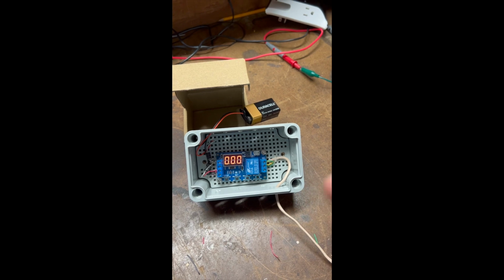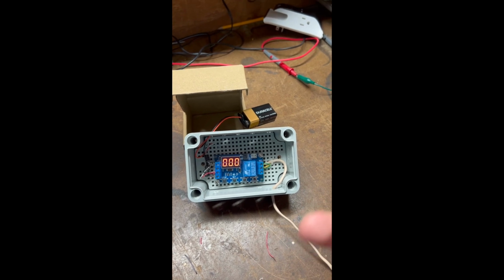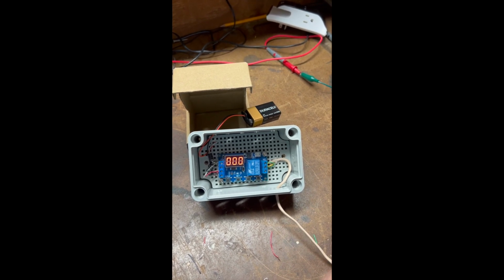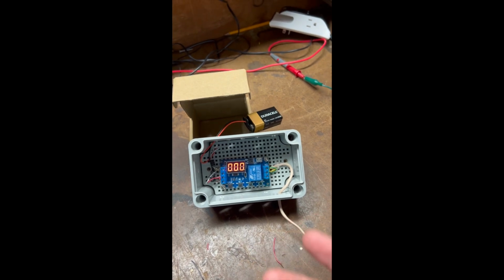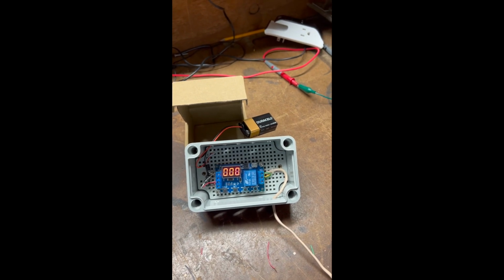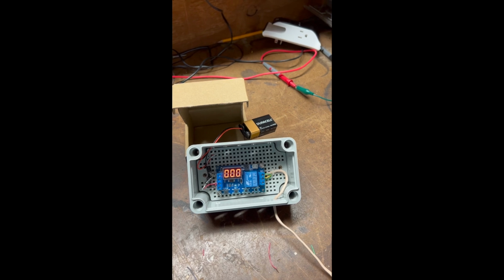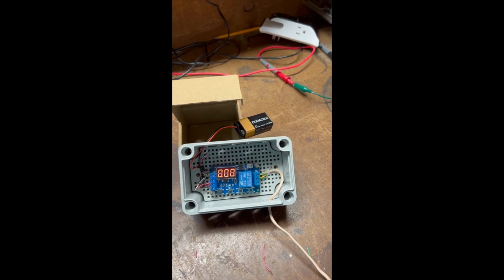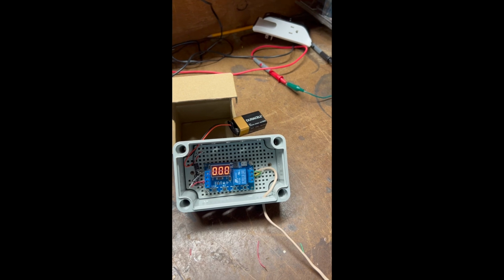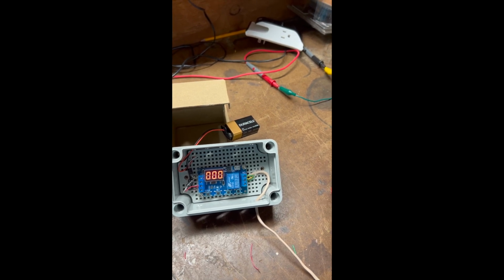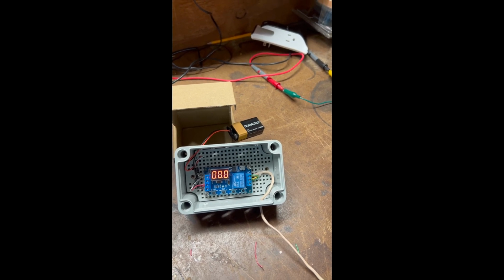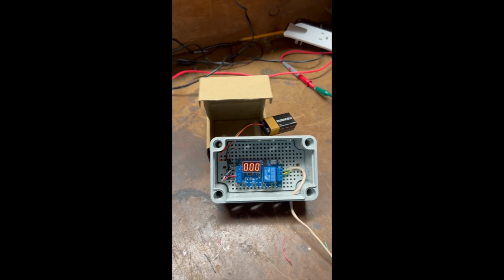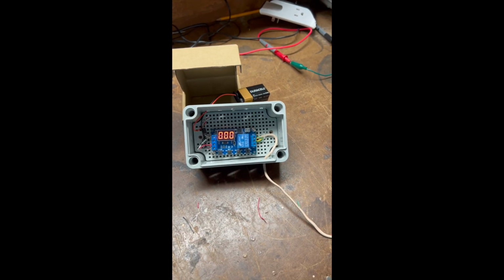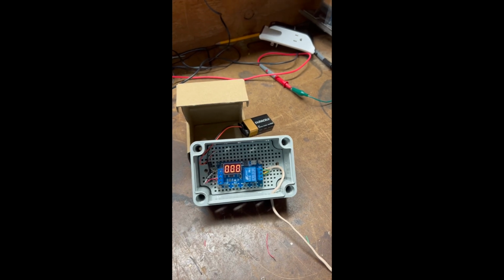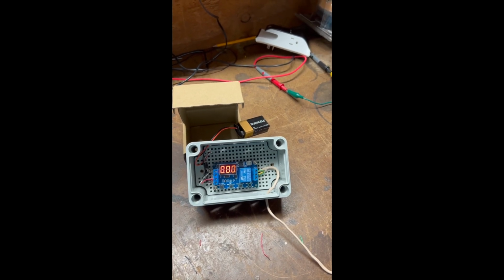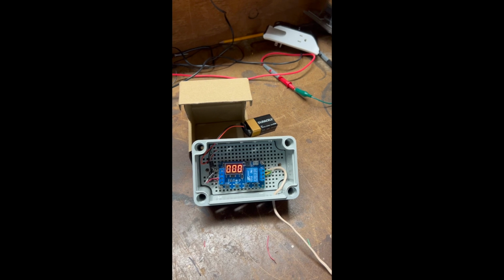The other situation is that this device was running in an always energized state, the way that I had it before. The relay was always energized, therefore keeping the normally closed contact open. So I was using about 96 milliamps of power to keep that energized all the time. Not a huge deal, but I thought about, well, what's the lifespan of a relay that's energized all the time? If that relay were to fail, then I could essentially get a false alarm and then have to replace my relay.